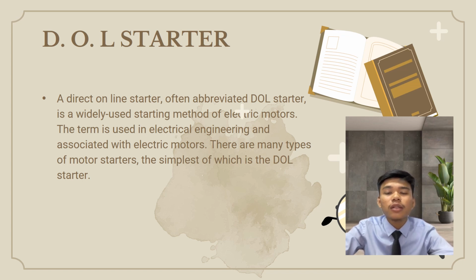A very well-known motor starter is the DOL starter of a 3-phase squirrel cage motor. This starter is sometimes used to start water pumps, compressors, fans, and conveyor belts. With a 400 volt, 50 Hz 3-phase supply, the power circuit connects the motor to 400 volt.